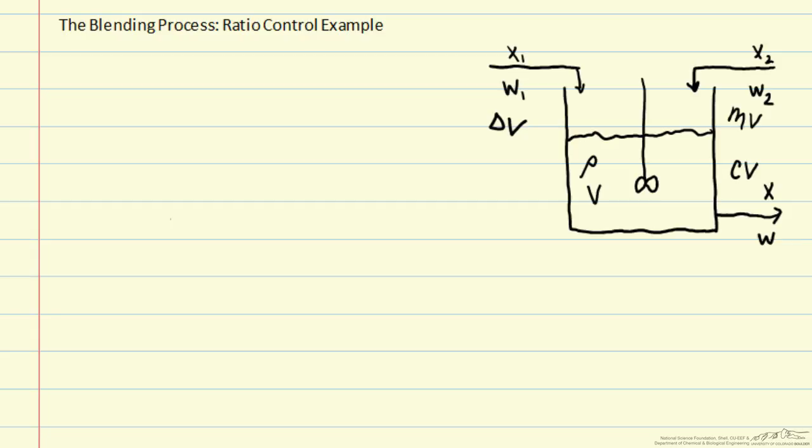In the last screencast, we went through the general concept of ratio control, which is a type of feedforward control. Specifically, we measured the disturbance variable W1 and then adjusted W2, the manipulated variable, in order to hold the two mass flow rates at a fixed ratio. And based on the steady state values we've been using in previous screencasts, we decided to keep them at a ratio of 3.